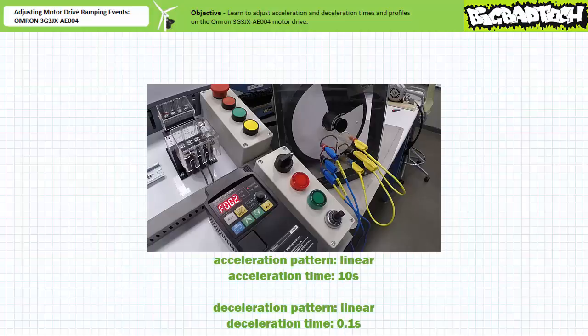Our first iteration is a linear acceleration pattern with a 10 second ramp up time and a linear deceleration time of 0.1 seconds. This extremely short deceleration period is essentially equivalent to instantaneously disconnecting the motor from supply voltage and letting it free spin to a halt. Letting a flywheel of this mass free spin to a halt takes an appreciable amount of time — 5 minutes and 48 seconds to be exact. We will not wait the whole time, but rather move through this experiment quickly, examining only the influence of acceleration times and patterns.